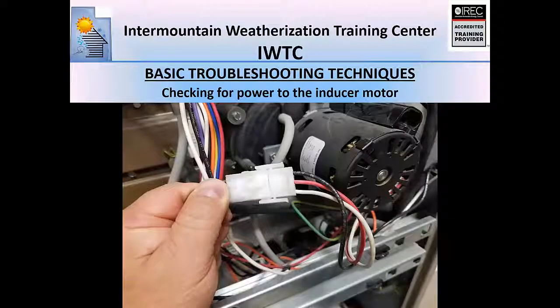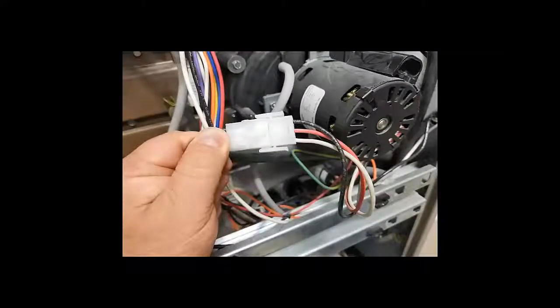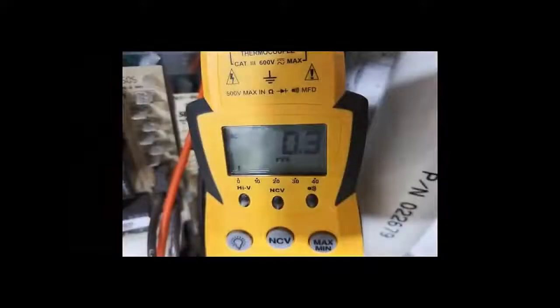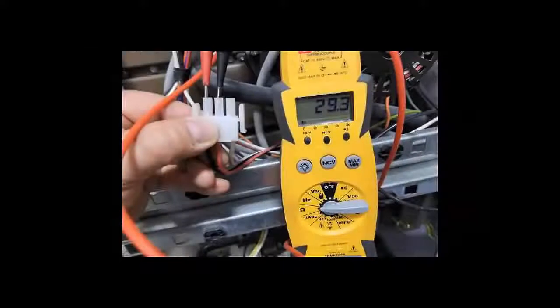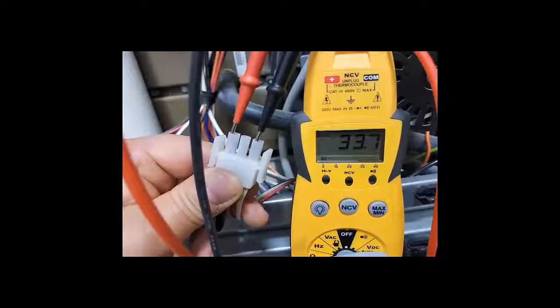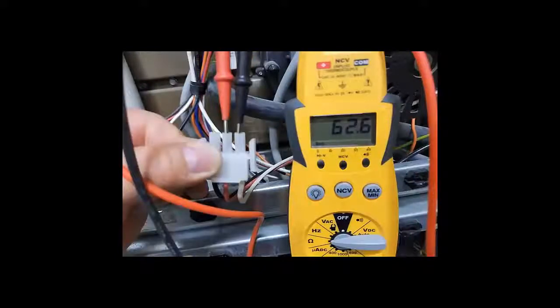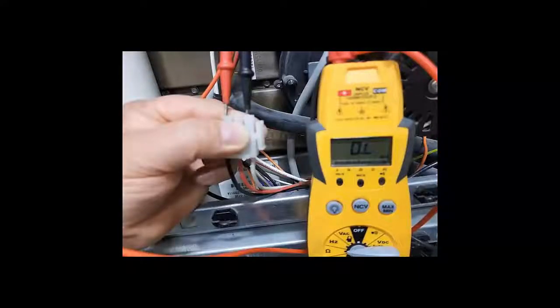Okay, so once we figured out that we do indeed have correct voltage to the motor, if the motor were not running, there's another simple check we can do to check the motor out and see if there's a problem with the motor. So we'll go ahead and show you guys that one. In order to check the condition of the electrical windings in the inducer motor, first make certain the main power is off and use an ohm meter to ohm the motor windings. To do this, just set your meter to the correct ohm settings and connect the leads to the wires leading to the inducer motor. If the motor windings are intact, you will get a resistance reading of some sort. If you get an open line, or OL as indicated by this meter, the motor windings are broken or shorted and the motor should be replaced.